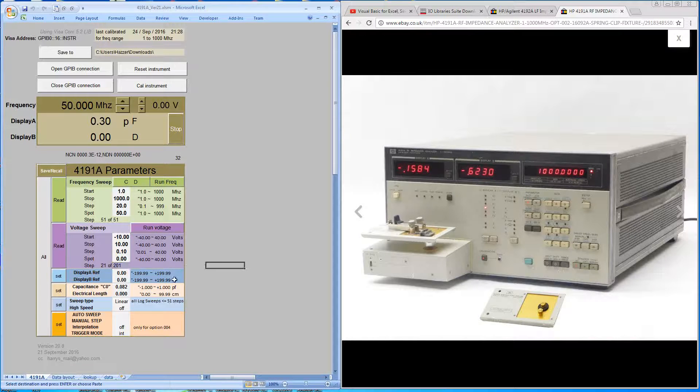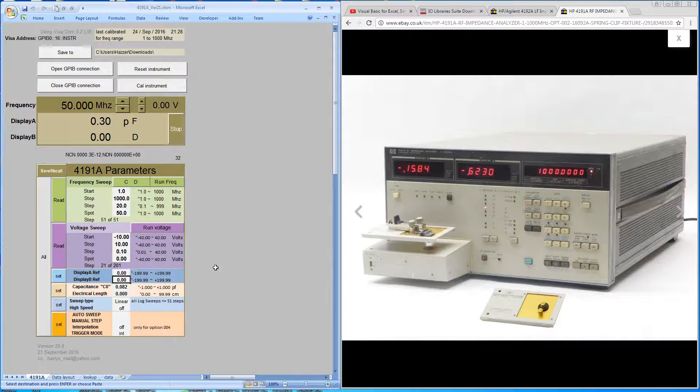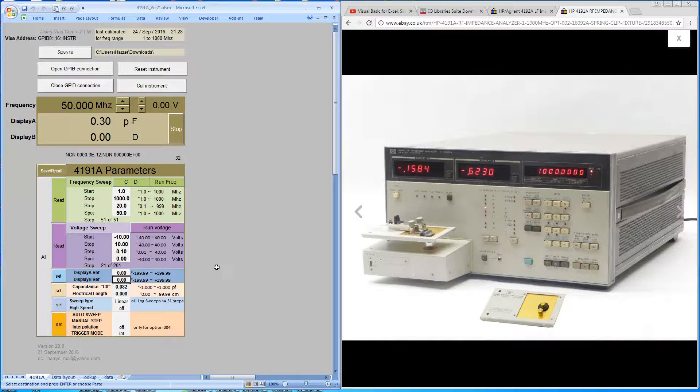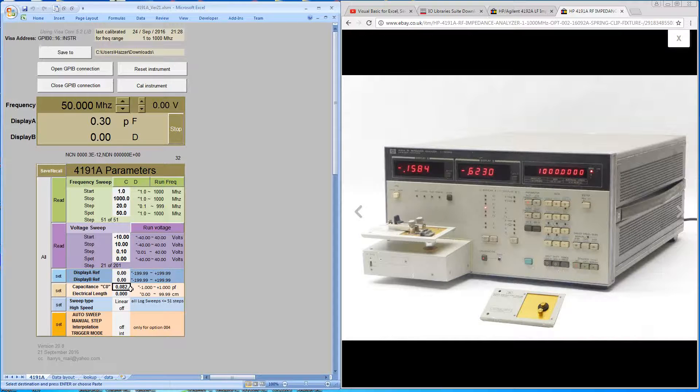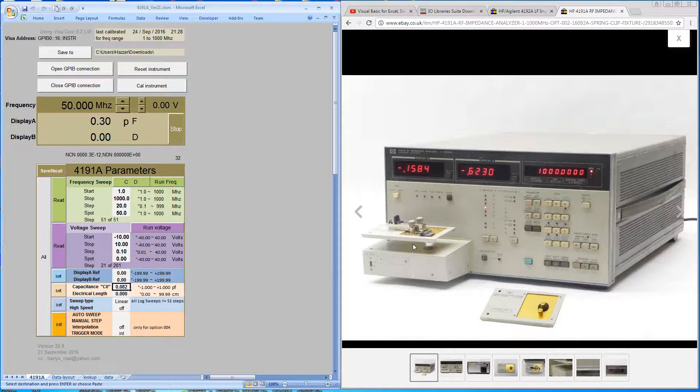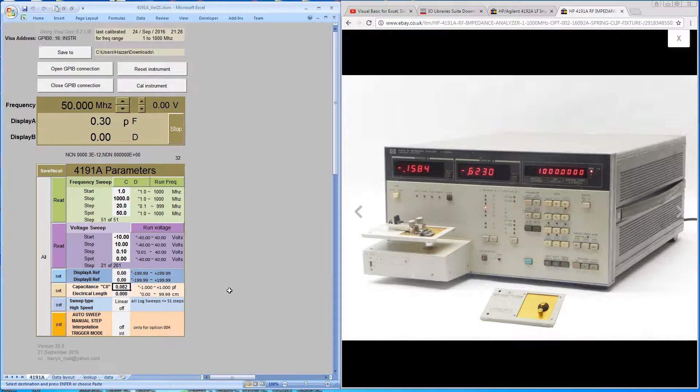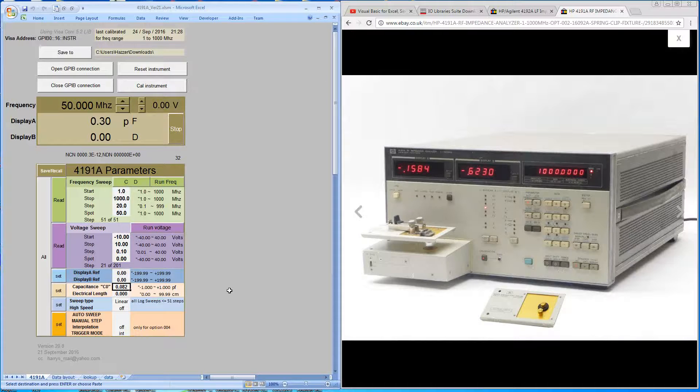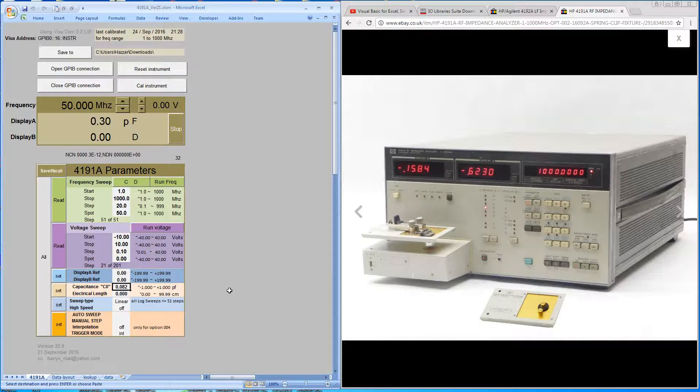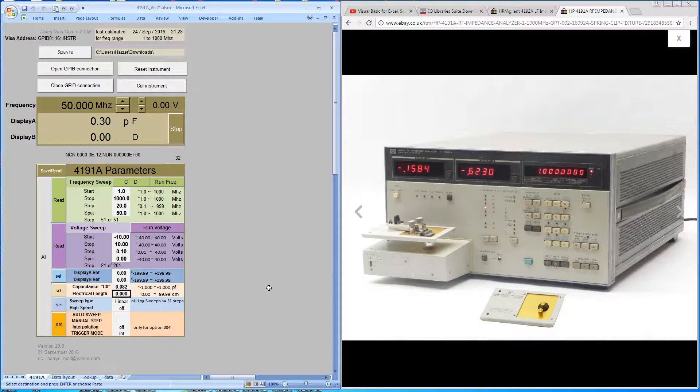You've got some offsets for the screen. So if you're doing component measurement, you can enter a default component and you can see how far it deviates from that component. This open capacitance refers to the APC7 connector and it's the fringe capacitance, which is the default value. If you're using a different test fixture, if it's got a different fringe capacitance when you're calibrating the machine, you'd enter that here. The electrical length is the distance that the calibration plane has been moved to your point of measurement.